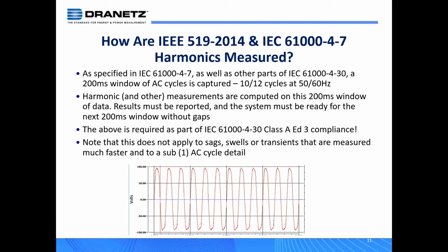But it's very important to note that these types of measurements, looking at 12 cycles or 200 milliseconds at a time, do not apply to sags or dips or swells or transients. They are looked at on a cycle by cycle basis by the instruments, which is also required by 61000-4-30, certainly for sags and swells. 61000-4-30 does not define transients. So the higher speed power quality events are looked at in cycle or sub-cycle detail, and these are for slower types of events, and of course harmonics falls within that category.